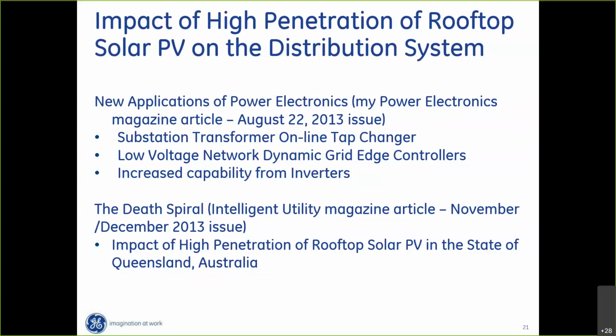Remember, these tap changers in substations are mechanical devices — 16 raise positions, 16 lower positions, a neutral position. Each mechanical change is a 5/8% change in voltage, but they're mechanical controllers not designed for that much duty cycle.